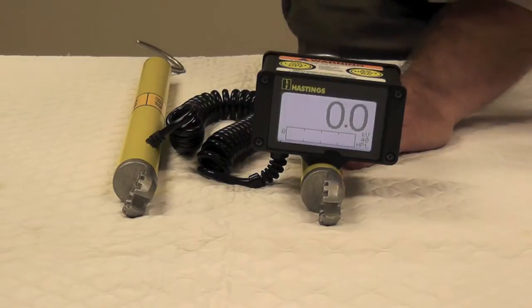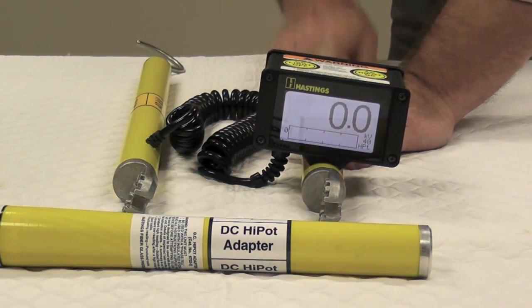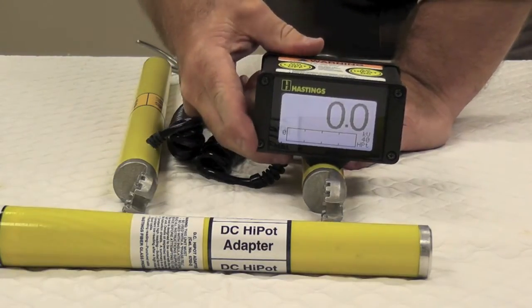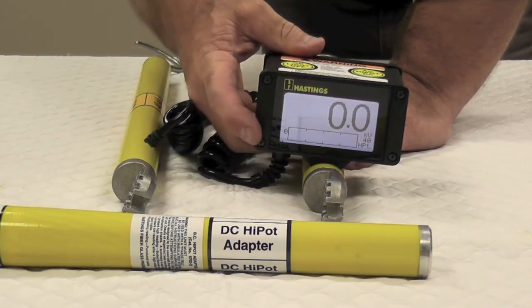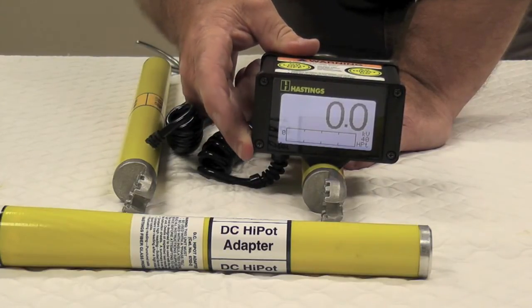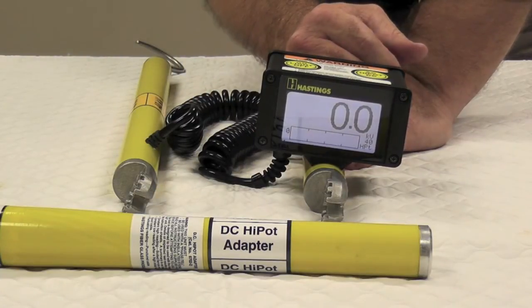Now when hipotting, you must use the HiPot adapter on the metered unit. There have been a couple of changes to this unit when doing the HiPot function. Number one, it holds your starting voltage when you're hipotting inside of the bar graph window. And number two, it will show 100% of your source voltage.